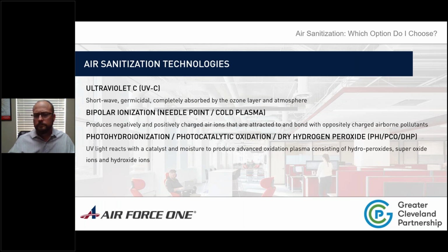Yeah, UVC—this is a trap we've had a lot of customers get into, and I'd like to clarify this for everybody on this call. It is a great point-of-use and surface sanitizer when installed inside your equipment, specifically facing the cooling coil, whether it's chilled water or direct expansion. It keeps you from forming fungus and bacteria and other things because it's a wet surface—it's so cold, it's constantly building up moisture, and it does a great job of that. Beyond that, it doesn't do anything for the rest of your system.